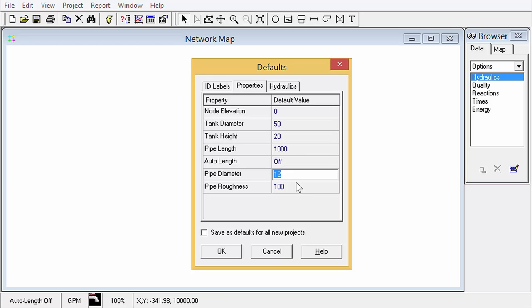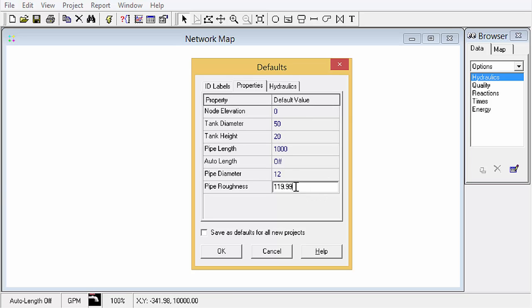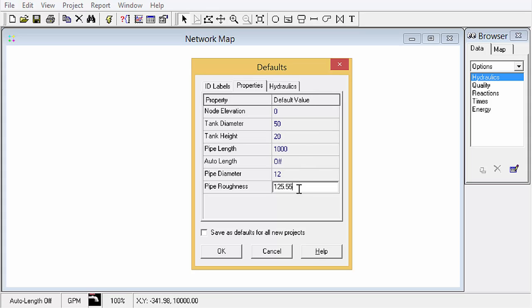You've got a default pipe diameter and a roughness. A lot of times what I'll do is choose a more realistic one but put a flag value off to the end like 119.99. The 0.99 is kind of a flag value. You can do anything like 125.55. It's really the decimal part that gives you an indication that no engineering judgment was used in determining that roughness. But then when you get into calibration you can round those off and use a more thought-out value.